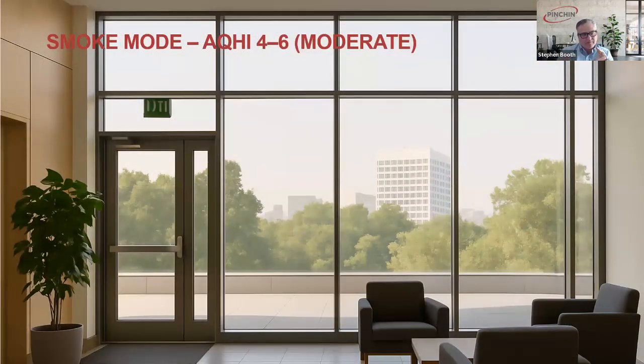So the ASHRAE document suggests a smoke mode operation. That is a moderate version that kicks in at air quality health index 4 to 6. You're starting to switch to recirculation mode on your HVAC system. You're minimizing the outdoor air to code allowed minimums. You're disabling those economizers on those demand control ventilation systems to avoid bringing in more outdoor air, and you're ensuring those MERV 13 plus filters are installed and functioning. You're closing windows, rooftop access, vestibule doors, reducing entry, limiting or postponing non-essential outdoor maintenance. So, maybe this isn't the time to be doing the roofing work, not the time to be doing the landscaping or a window washing project when we're starting to get into these moderate smoke levels.